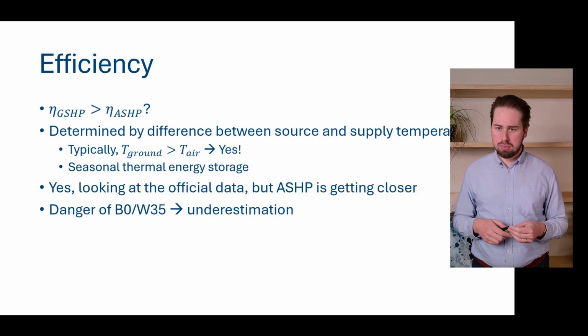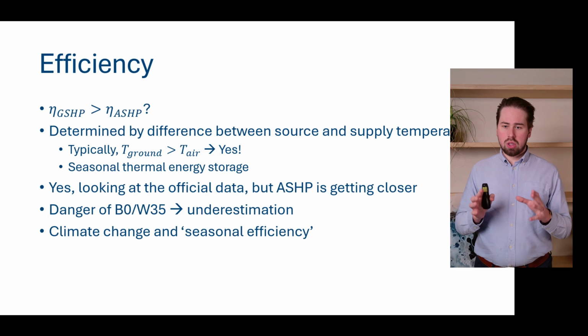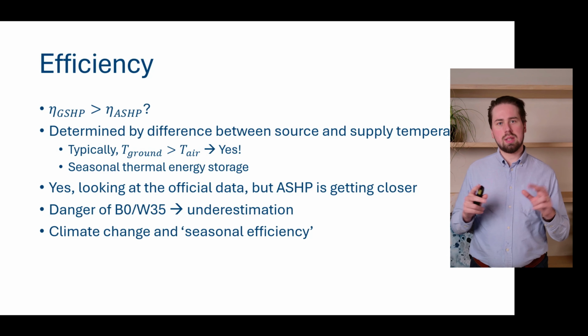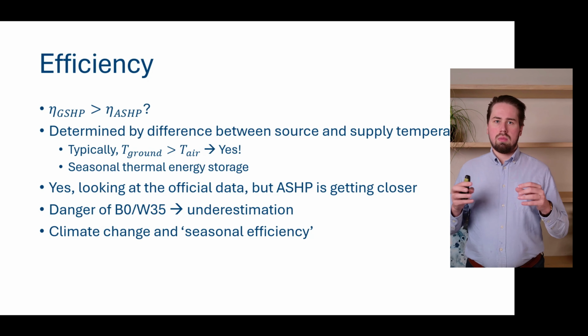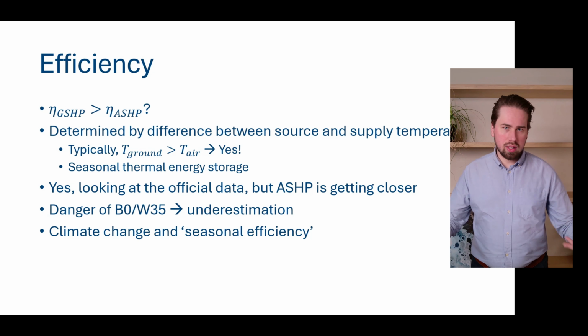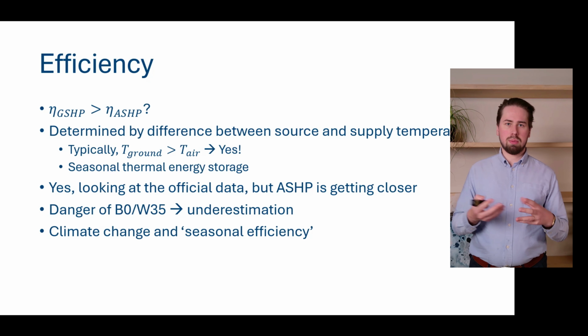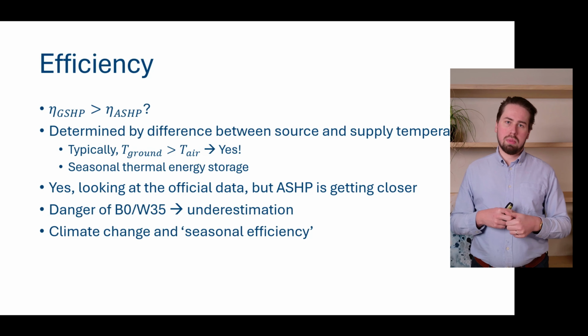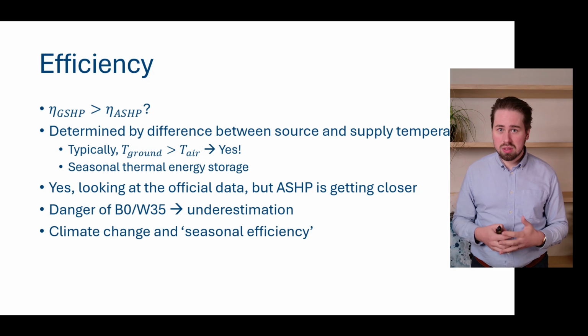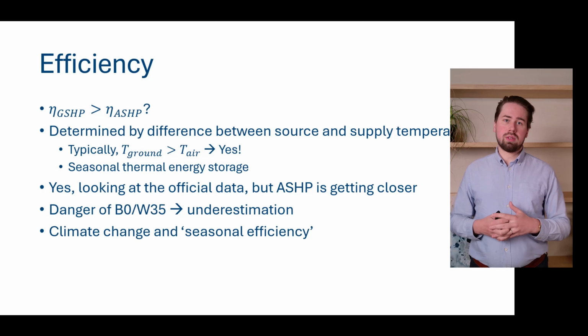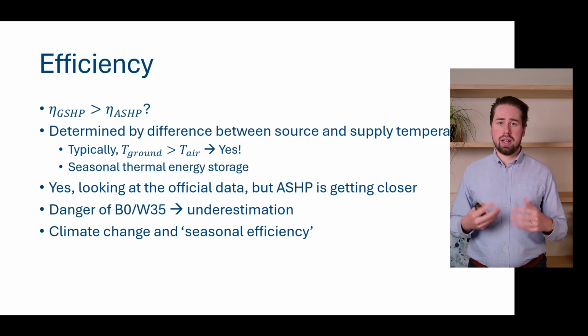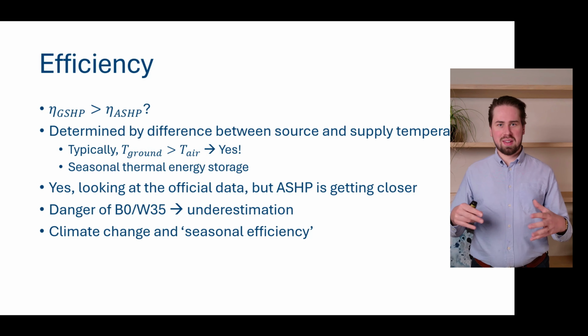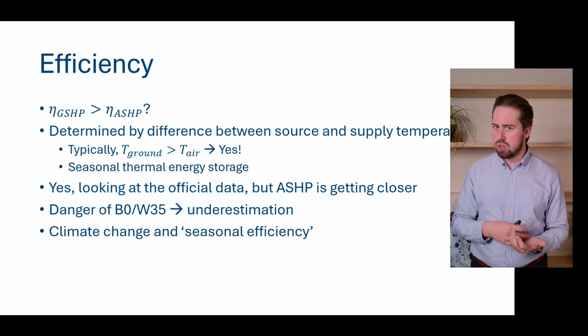And then we also have the problem of climate change and the concept of seasonal efficiency. Perhaps at the coldest time in winter this reasoning holds and our ground source heat pump is more efficient than our air source heat pump. But in mid-season, when it's 15 degrees outside and we want to heat up to 20 degrees Celsius, probably our air temperature is higher than our ground temperature and our air source heat pump is more efficient. So with climate change and everything heating up, perhaps our air source heat pumps are automatically becoming more efficient than our ground source heat pumps.